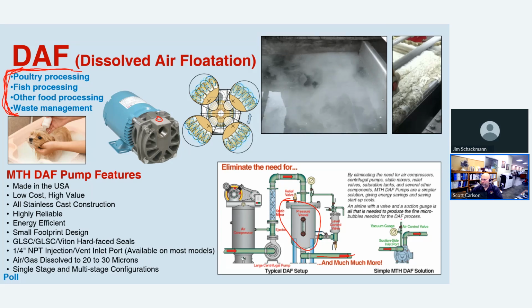All of this equipment requires maintenance, and all of it is pretty expensive to be able to start up. So by using a regenerative turbine pump, the only things required are a vacuum gauge, a line into the inlet, as well as a couple of valves on the ends to get it set up. So once it's set up, you have to put a little suction pressure on it, a little bit of discharge pressure on it, and kind of fine tune those three factors. Once you get that solution using a regen turbine, it's pretty much a set it and forget it type situation. So you can replace all this equipment with just a single pump.